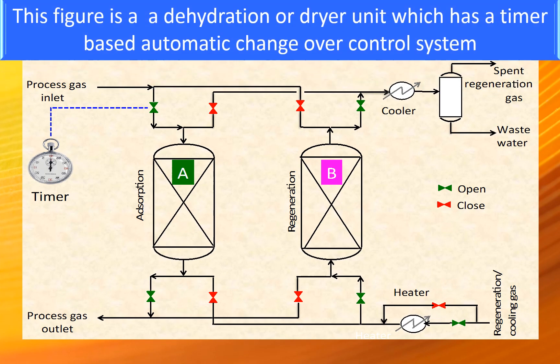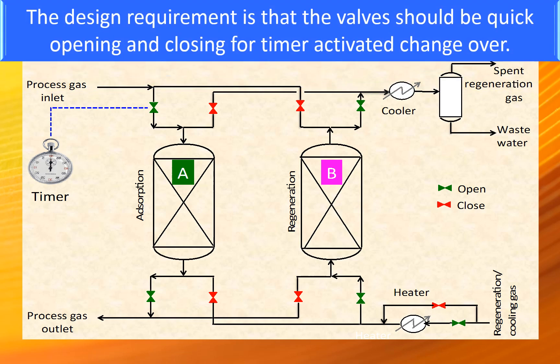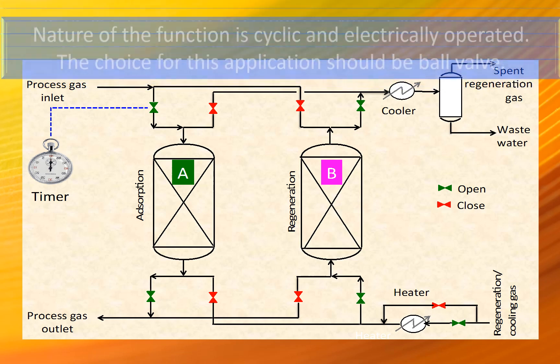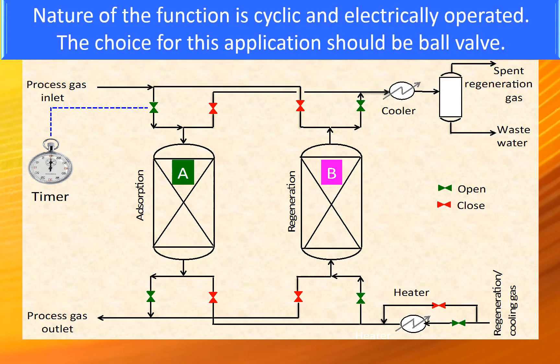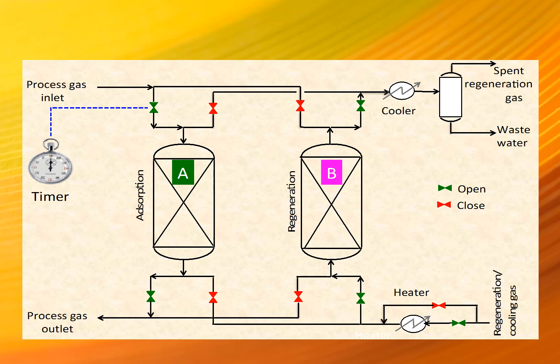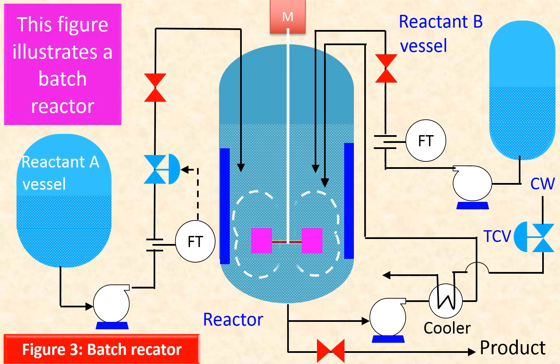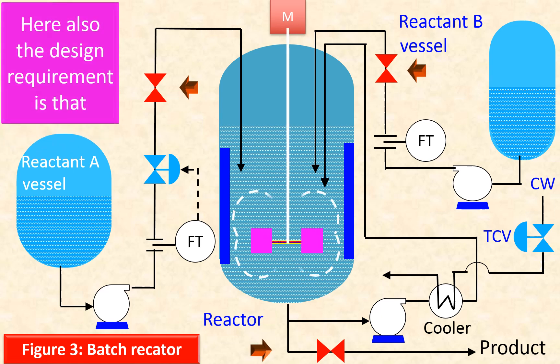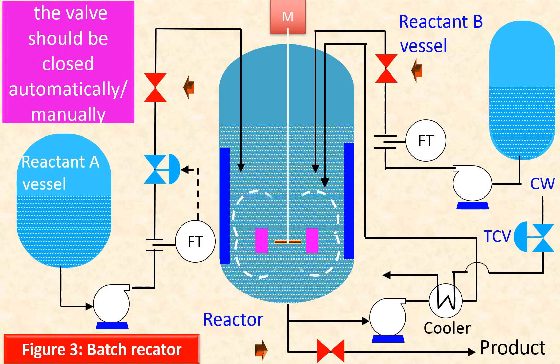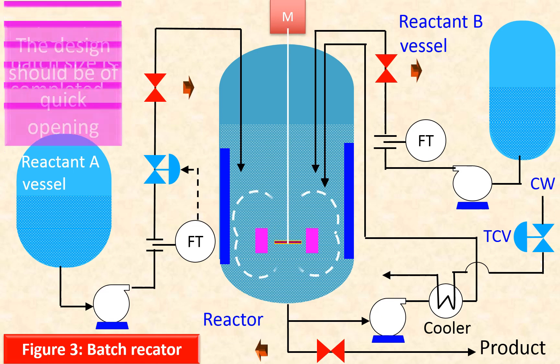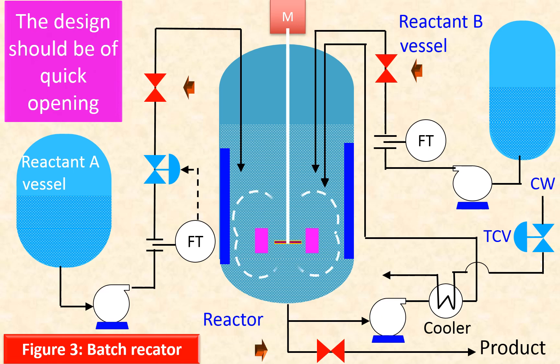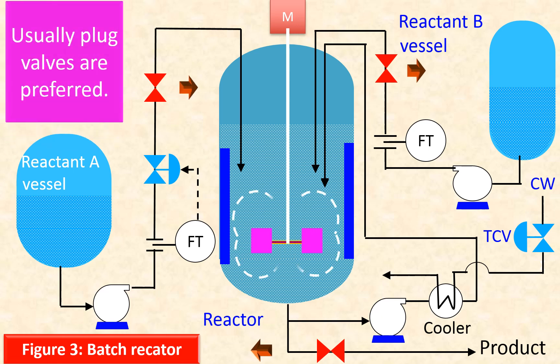This figure is a dehydration or dryer unit with a timer-based automatic changeover control system. The design requirement is that the valve should be quick opening and closing for timer-activated changeover. The nature of the function is cyclic and automatically operated — the choice for this application should be a ball valve. For the batch reactor, the design requirement is also that the valve should be closed automatically or manually when the batch size is completed, with quick opening capability. Usually plug valves are preferred for this application.